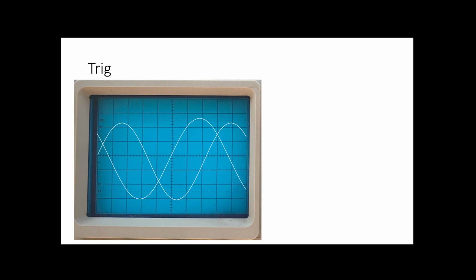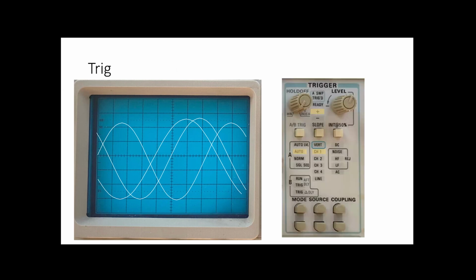And it will continue displaying. And this time when it gets to the right-hand side, it's away down at the bottom of the graticule. And when it flies back, it'll do that. And you end up with this spirograph display, as I call it, on your screen. Because the same wave keeps getting displayed, but it keeps getting thrown from a different point on the left-hand side, because whenever the spot got back to the left-hand side, it just kept tracing. So in order to stop that from happening, we use what's called the trigger system on the scope.